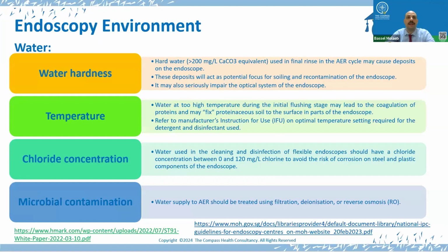Now, talking more about the environment, let's address the water issue. Water hardness is an important element we need to be aware of. Hard water used in the final rinse in the AER cycle may cause deposits on the endoscope. These deposits will act as a potential focus for soiling and contamination of the endoscope, and may also seriously affect the optical system of the endoscope.